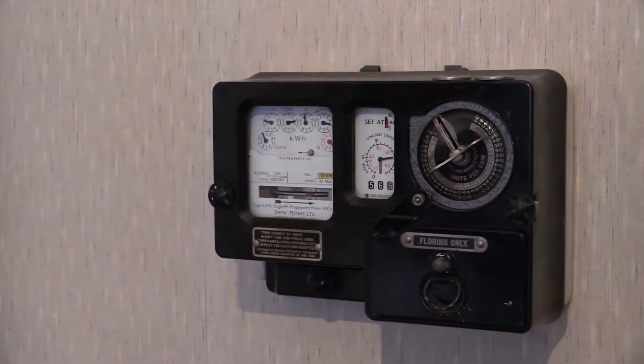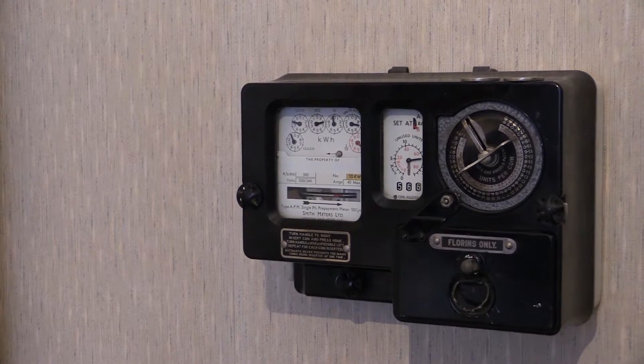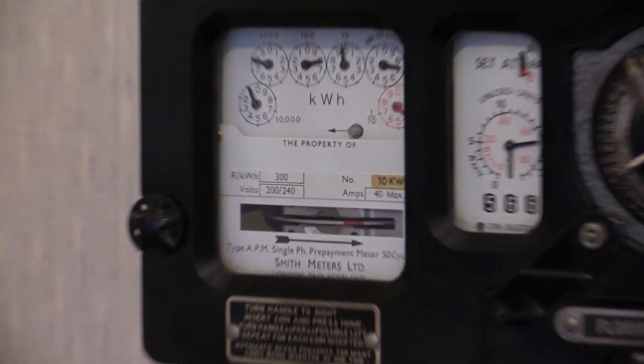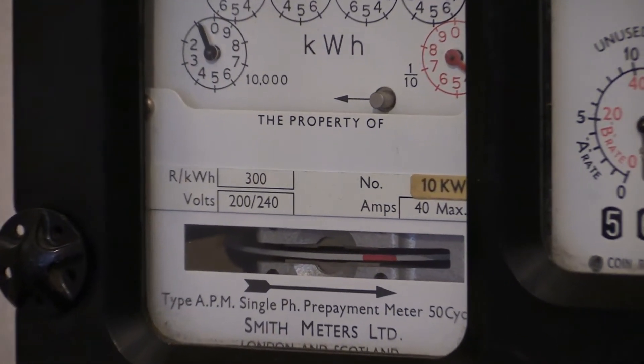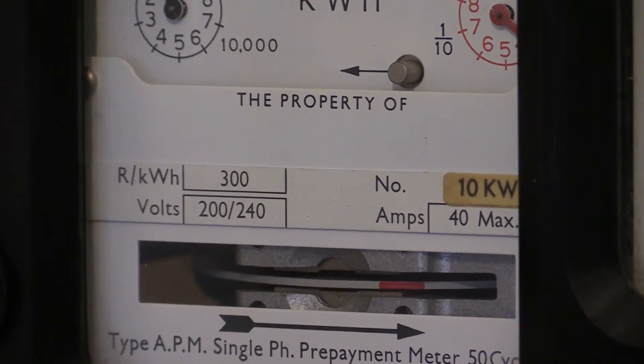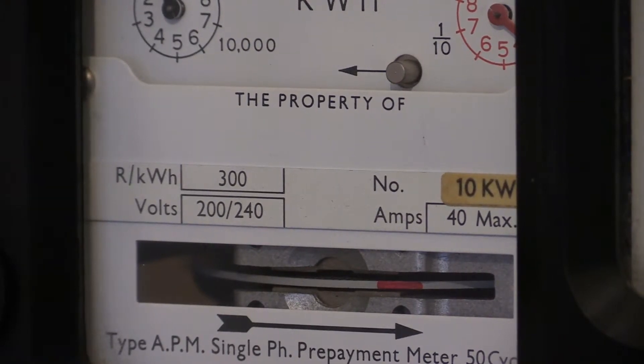Let's go over to the kilowatt hour readout and look at the characteristics for this one. It's a single phase, two wire instrument, 200 to 240 volts, 40 amp maximum. The load wheel characteristic is 300 revolutions per kilowatt hour, which is a bit slower than the previous APM which ran at 360.